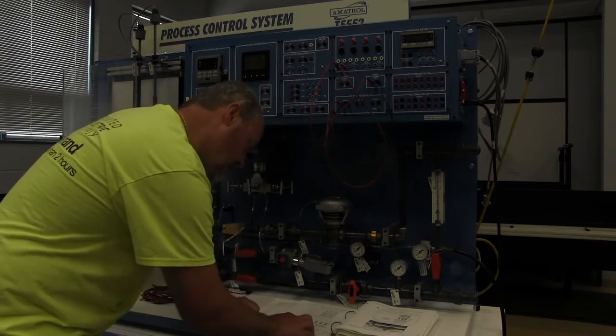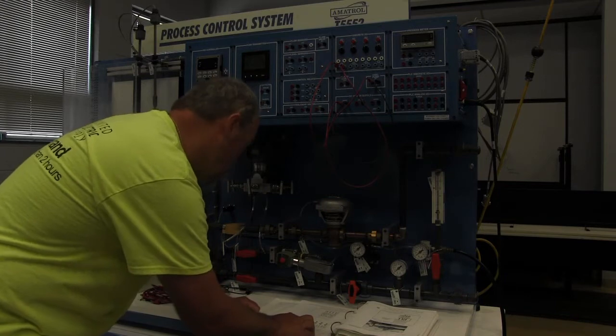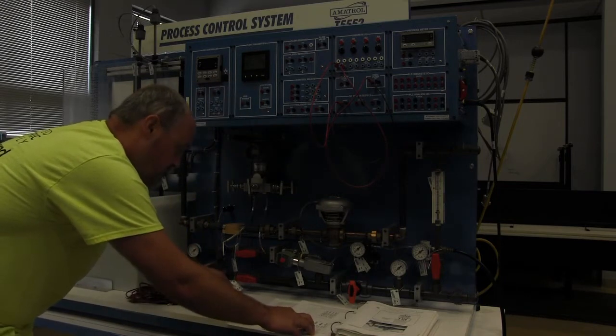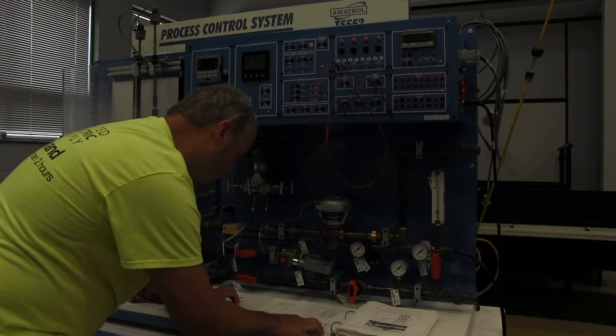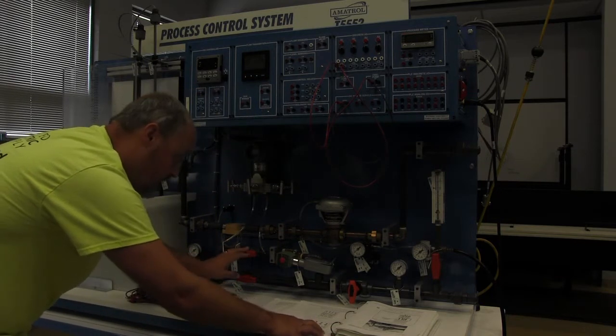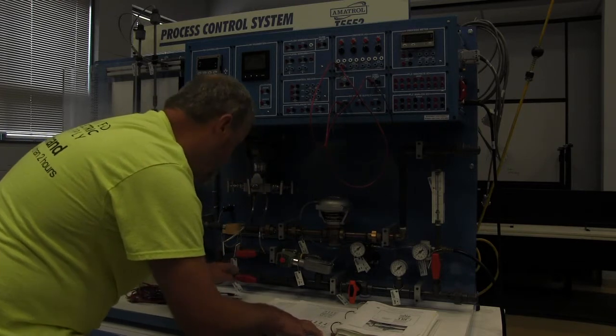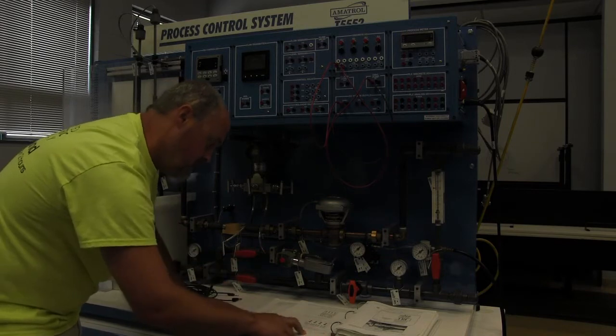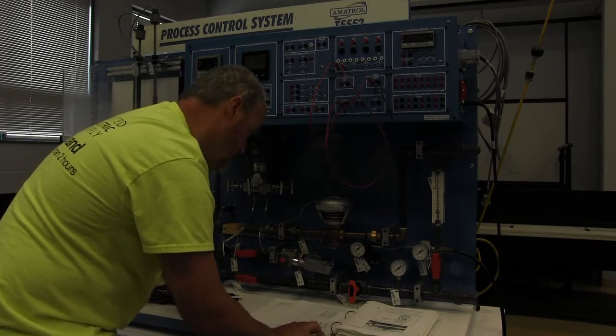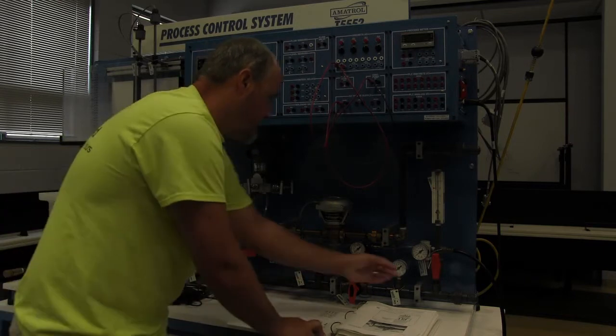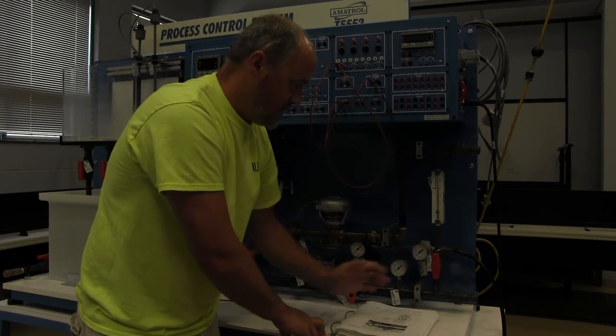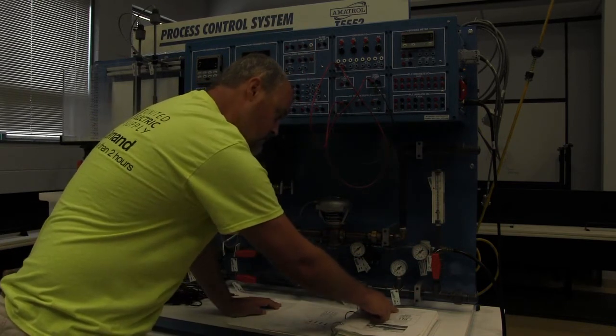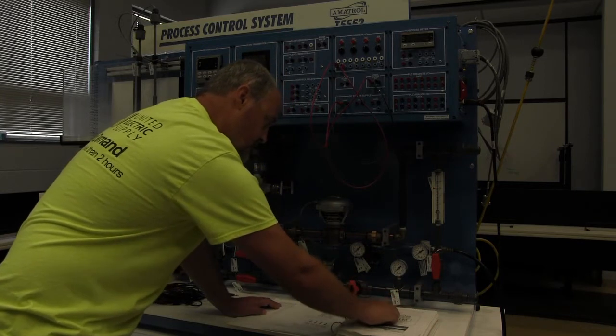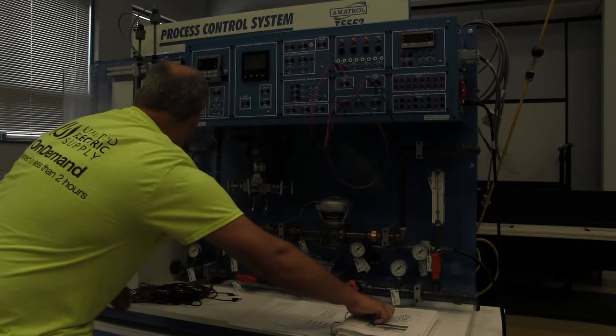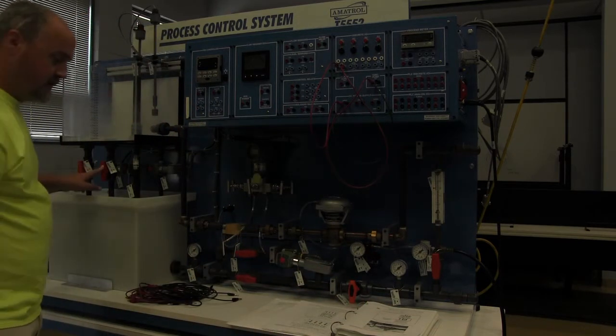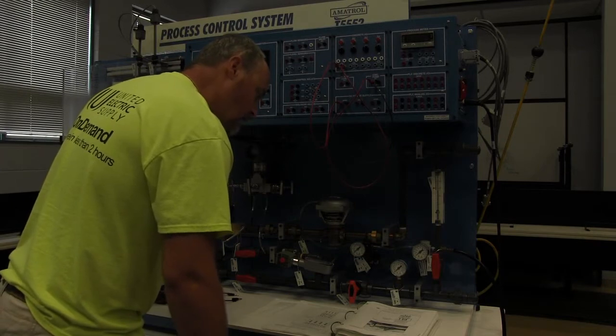And then it says make sure the hand valves HV100B and HV100A in the process piping are both fully open. They're in line with the pipe, so they are open. Make sure the flow control hand valve 100D is fully open. 100D is over here. 100D is in line with the pipe. It is open. Make sure the two process tank manual drain valves HV300 and HV100C are closed.